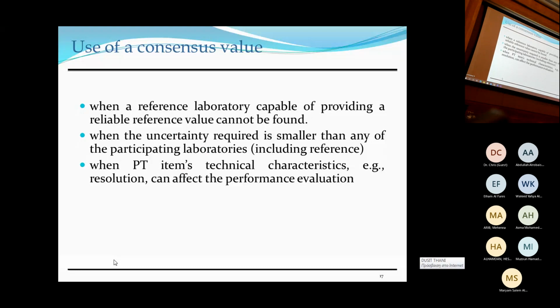When would a consensus value be used? When a reference laboratory capable of providing a reliable reference value cannot be found. So you don't have such a lab. That's a rare situation, but it could happen in certain areas. Also when the uncertainty required is smaller than that of any of the participating laboratories.